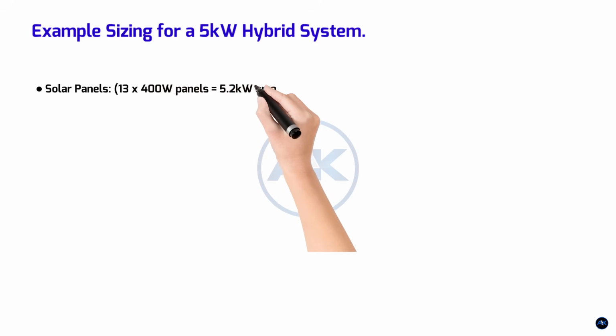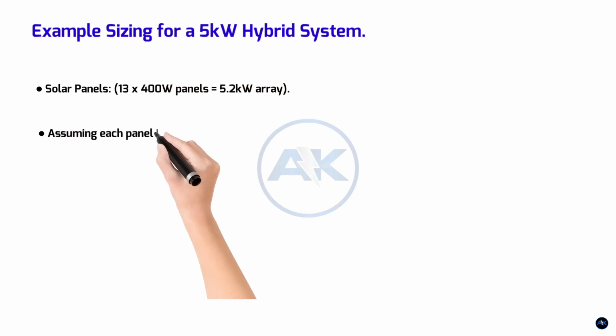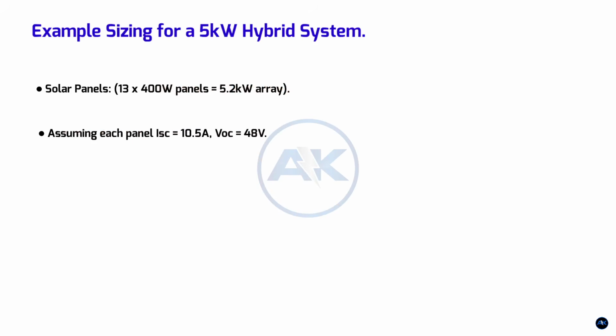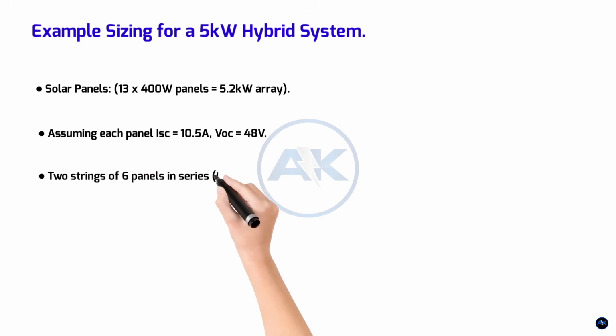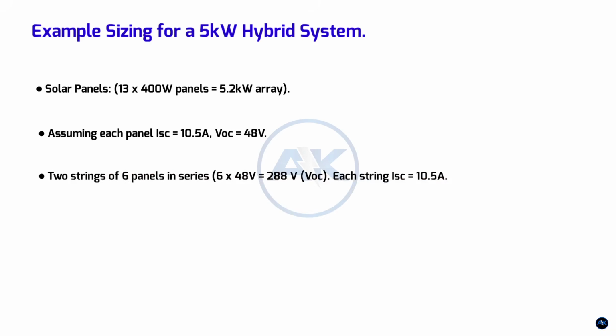Example sizing for a 5 kilowatt hybrid system. Illustrative, consult professional. Solar panels: 13 times 400 watt panels equals 5.2 kilowatt array. Assuming each panel ISC equals 10.5 amps, VOC equals 48 volts. Two strings of 6 panels in series. 6 times 48 volts equals 288 volts. Each string ISC equals 10.5 amps.